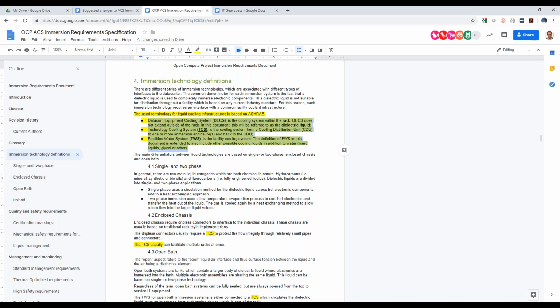Now, that is correct. It's basically taken the central heat exchanger and extended it out to a larger footprint to support multiple racks. The question to then look at is, from that CDU to the facility water system, does that have a break into it that goes through to another system, or is it directly through a facility water system, directly to a heat rejection tower?